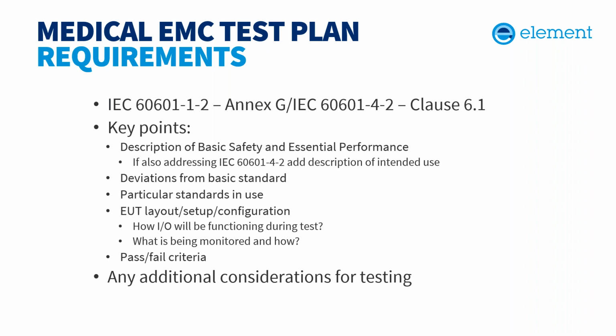And then layout and configuration. How is the product going to be set up? How is it being run and exercised during the testing? Also be aware that with -4-2, because you're monitoring intended use versus the basic safety and essential performance, you may need to do each immunity test more than once to cover the different use case. So it's also important to examine the risk for all potential modes of operation and consider testing them.